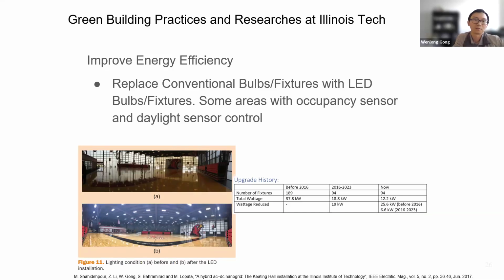So here is a more detailed example. Keating Hall, we replaced all the conventional fixtures with LED fixtures, and I logged all the upgrade history. We upgraded 2 times. Before 2016, it was using 189 fluorescent fixtures, and the total wattage was 37.8 kilowatts. In 2016, we replaced all these old fixtures with 94 LED fixtures, and the total wattage came down to 18.8 kilowatts. It cut down almost half.